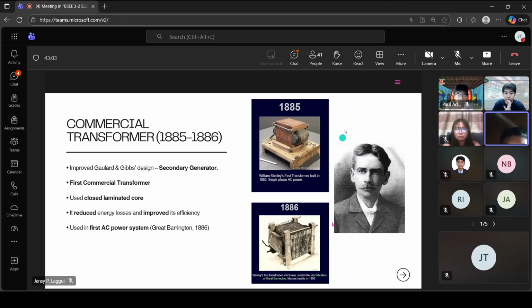In 1885, Stanley redesigned the entire device and introduced the closed laminated iron core. A closed core means the magnetic path is complete, so almost no energy escapes. A laminated core means the iron core is made of many thin sheets that reduce unwanted eddy currents. These improvements made the transformer much more efficient, more stable, and cheaper to operate.